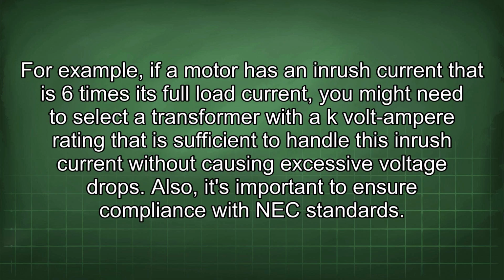For example, if a motor has an inrush current that is 6 times its full load current, you might need to select a transformer with a kV ampere rating that is sufficient to handle this inrush current without causing excessive voltage drops. Also, it's important to ensure compliance with NEC standards.